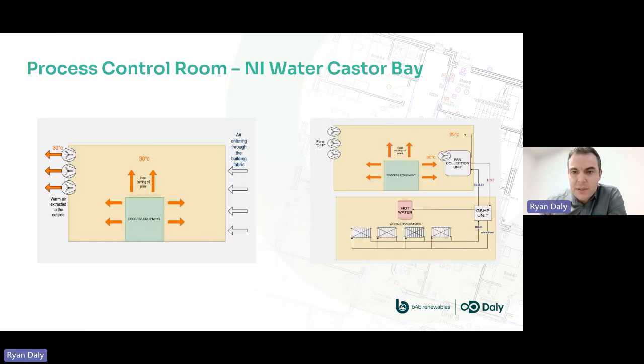This is a case study we'd completed about 3 years ago now. NI Water approached us at their Castor Bay site. So what they had was a process control room, which was sitting always at around 30 degrees all year round. Just equipment that was giving off a lot of heat, and they had 3 extract fans just dumping that heat outside. So we came up with a solution of a ground source heat pump with a fan collection unit.